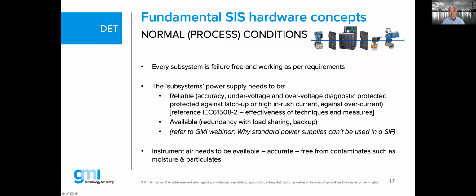Of course, your instrument air also needs to be available. And your instrument air is another weak point that sometimes in design can stop your instruments from doing the right things. It needs to be free from any dirt, from any contaminants, such as moisture or some specific items that are left behind in your pipelines. As some people will know, during commissioning and startup, you may find some weird things in your pipelines which do not belong in there, even in your instrument air pipelines, etc.